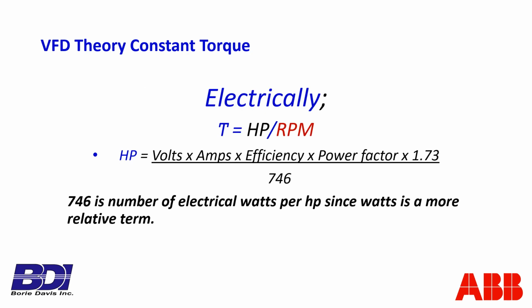So that's a mechanical grasp of the torque equation we've developed. Now we have to change it to an electrical equivalent. So mechanically, torque equals horsepower divided by RPM, as we said, and there's a constant 5250, but I left that out for purposes of simplicity. So electrically, horsepower is equal to volts times amps times efficiency times power factor times the 1.73, which actually is the square root of 3. That's in there because this is based on a 3-phase power equation. Divided by 746 watts, because watts is a measure of energy that is more useful than horsepower. So there are 746 watts per horsepower.